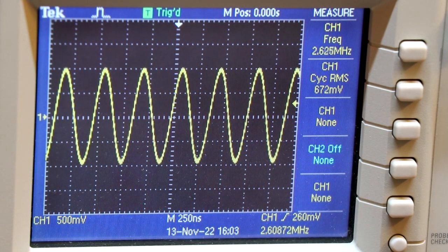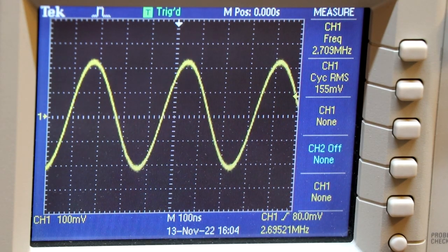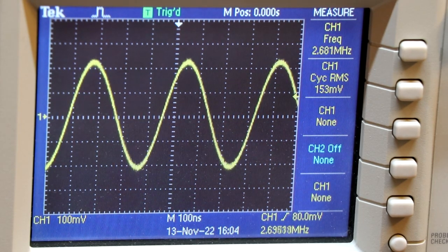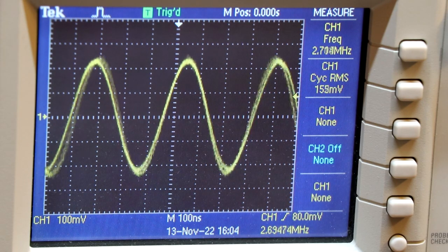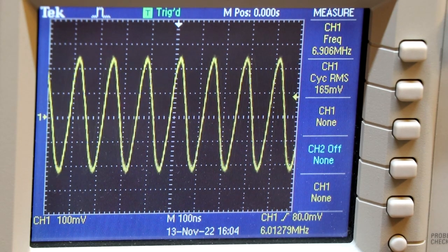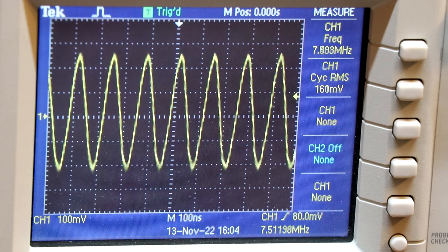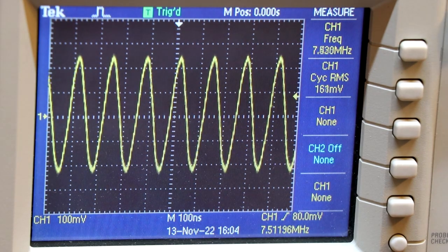Let's move on to the next range, which is 2.7 to 8 MHz. So the amplitude has dropped off a little bit, but it is actually reading around 2.7 MHz. Let's go to the top end of the range, which will be 8 MHz. And this time it's reading just a little bit low at 7.5 MHz.